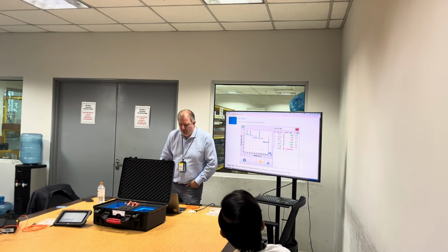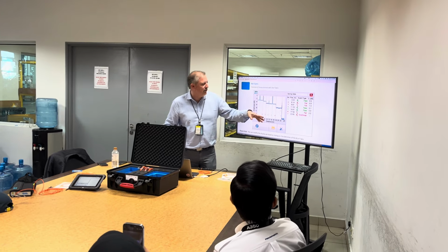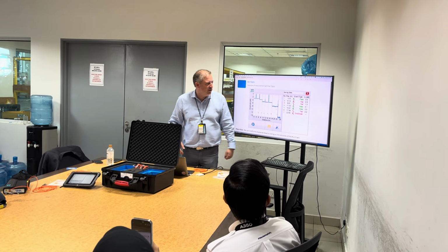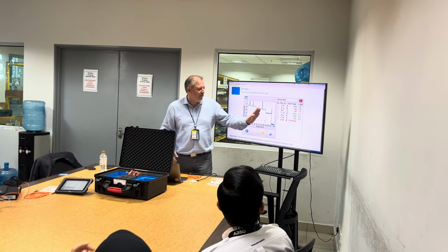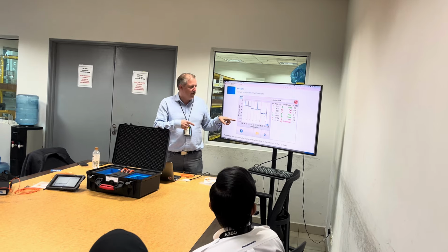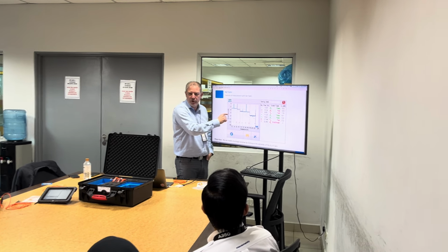And this is one example of measurement. Obviously, this is an example with a lot of issues, a lot of connections, a lot of damage. This is how it's going to look. You're going to have the graph on one side, distance and amplitude, as I showed you before. I told you you're not going to have a slope because we don't have much attenuation.